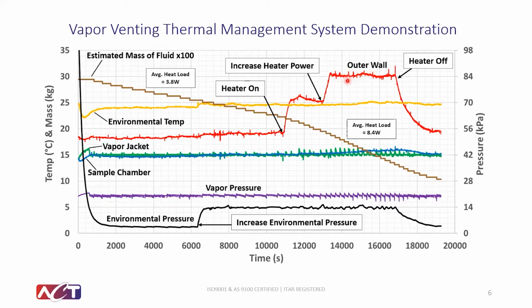So during this time, we can see a few changes. First, an increase in frequency of the fluctuations in the vapor pressure due to the increased frequency at which the valves had to open to dissipate the higher heat load. We can also see temperature spikes in the vapor jacket. This was due to slightly warmer liquid from the bladder entering the vapor jacket. And then we can see a change in slope of the estimated mass, indicating an increased heat load.